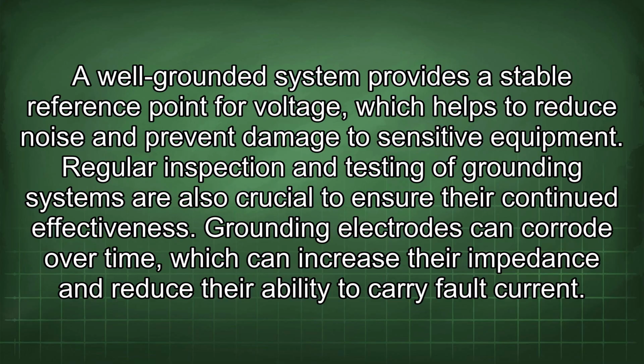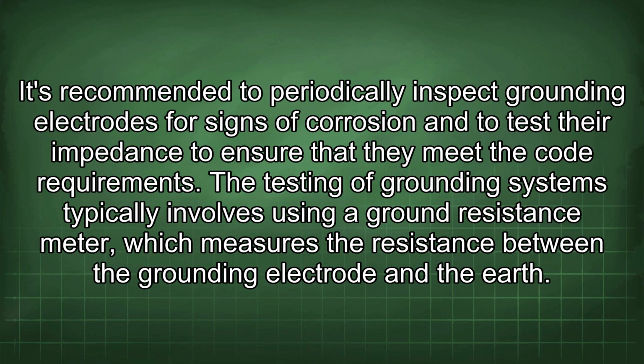equipment. Regular inspection and testing of grounding systems are also crucial to ensure their continued effectiveness. Grounding electrodes can corrode over time, which can increase their impedance and reduce their ability to carry fault current. It's recommended to periodically inspect grounding electrodes for signs of corrosion and to test their impedance to ensure that they meet the code requirements. The testing of grounding systems typically involves using a ground resistance meter, which measures the resistance between the grounding electrode and the earth.